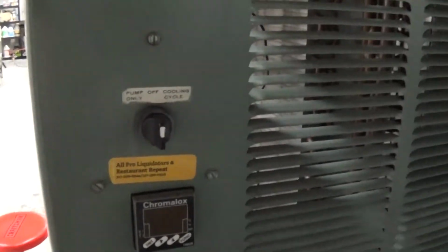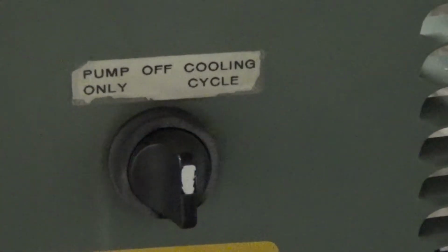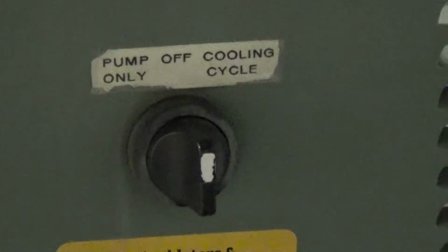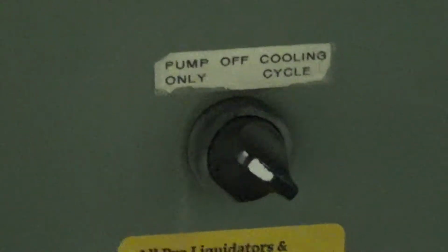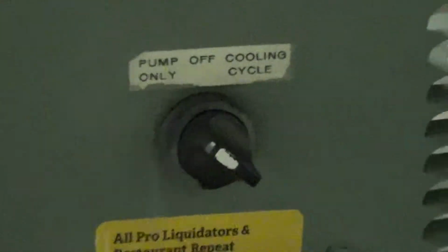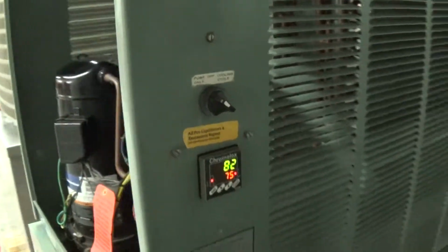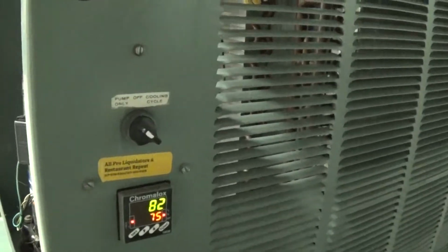So in this mode here, you basically have a selector switch which is off, pump only, and cooling cycle. We're just going to turn on the pump only.